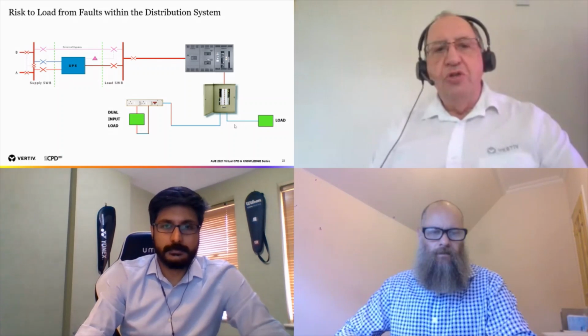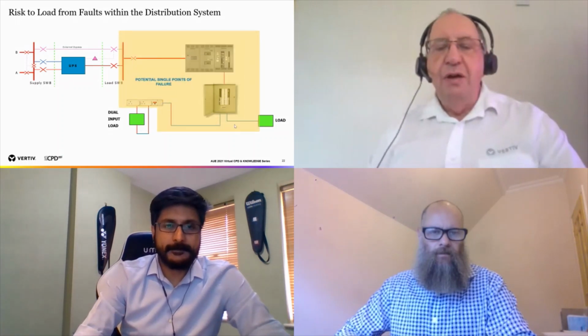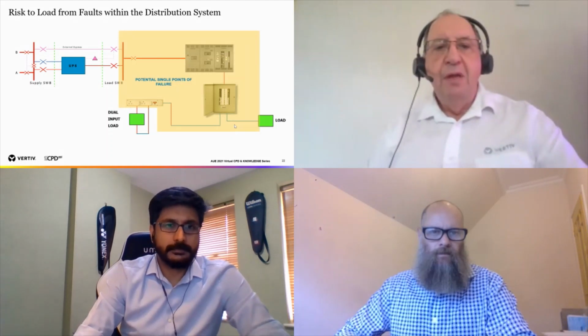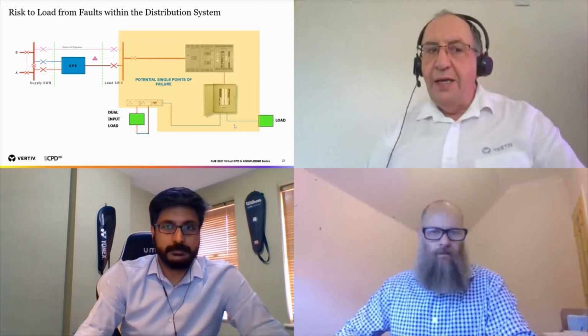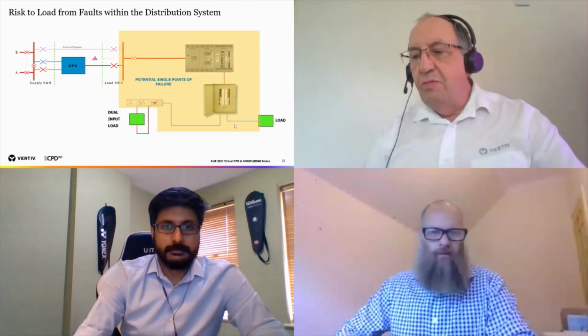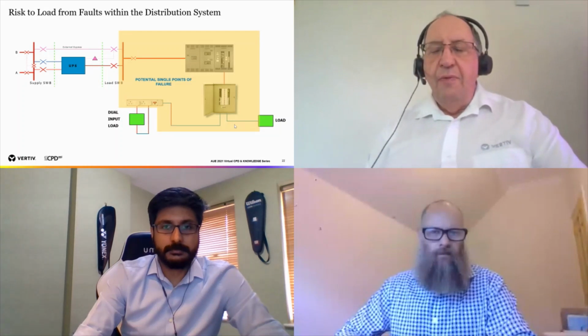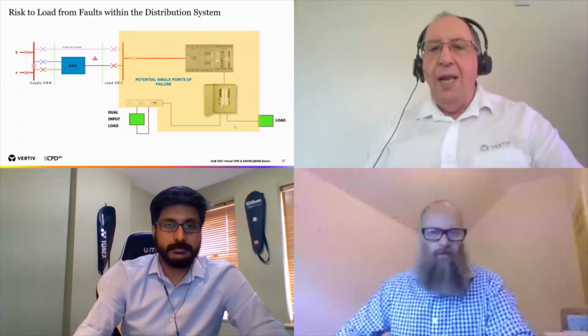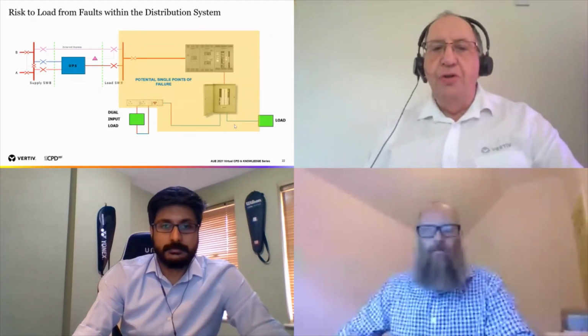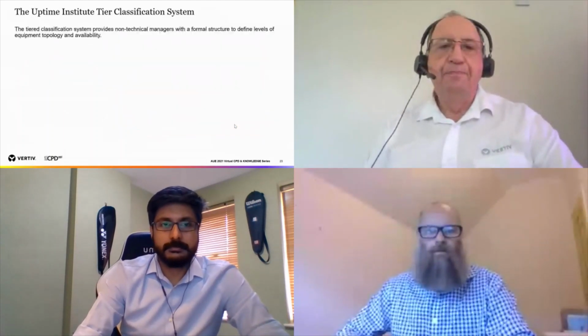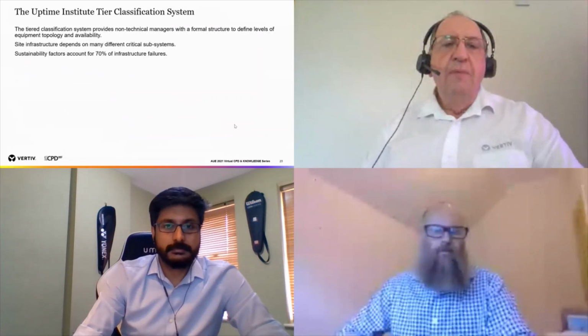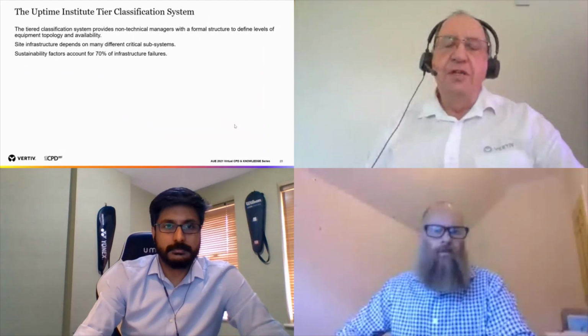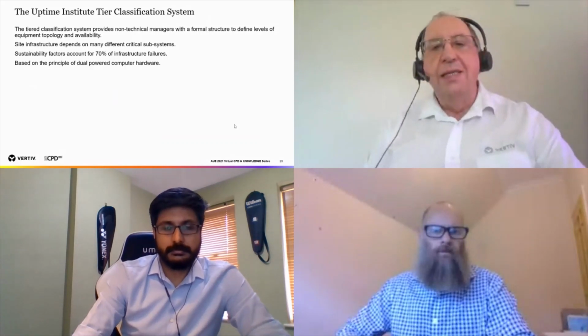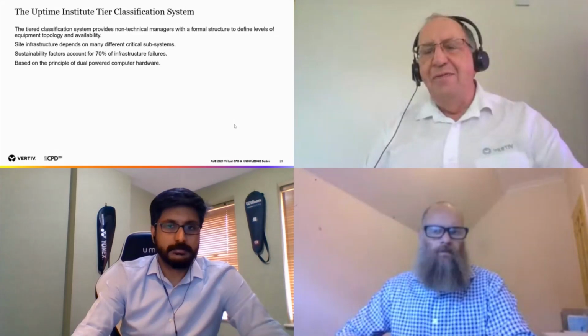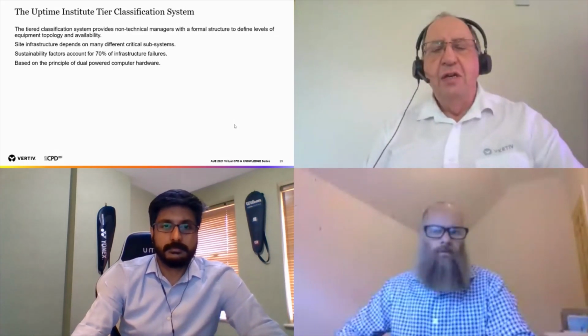So what we're trying to do is analyze this circuit to avoid single points of failure. And indeed, this technique can be used on mechanical systems as well, on cooling water systems, etc. So what we're trying to do is avoid a place that could shut the whole load down with a single point of failure. So we've got lots of different subsystems within a system, and sustainability or maintenance factors account for something like 70% of infrastructure failures.